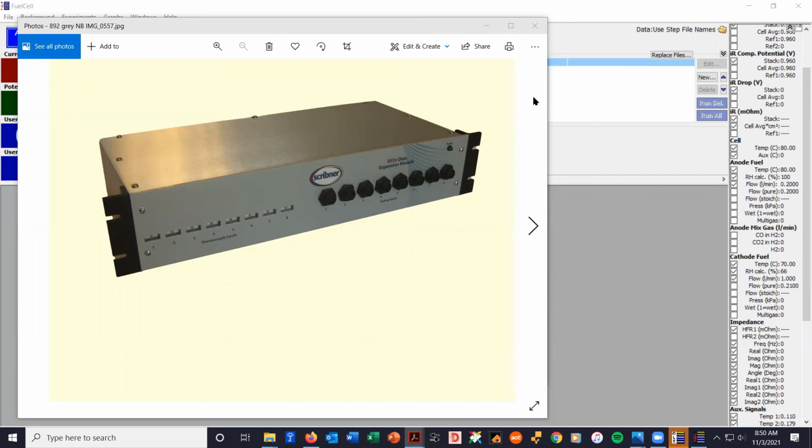Kevin, so in that case, if you'd like to measure the impedance when you use a potentiostatic measurement, you have to use the FRA on the potentiostat, and the rest of the time, for example, the HFR is done through the load. Yes, that's correct.